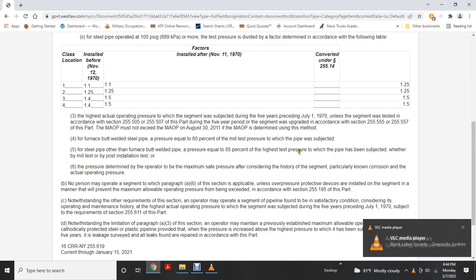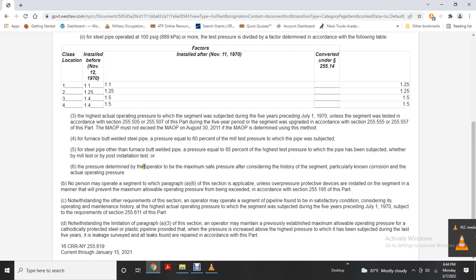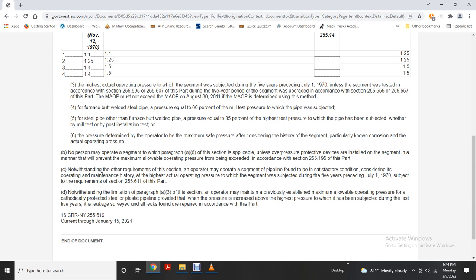For steel pipe other than furnace butt weld, the pressure is 85% of the highest test pressure for the pipe, subject to other mill test or installation test pressure. Determine the maximum safe pressure considering the history of the segment, particularly known corrosion and the actual operating pressure. No person may operate a segment covered by paragraph A6 of this section unless overpressure protection devices are installed on the segment in a manner that prevents the maximum operating pressure from being exceeded, in accordance with 255.195 of this part.